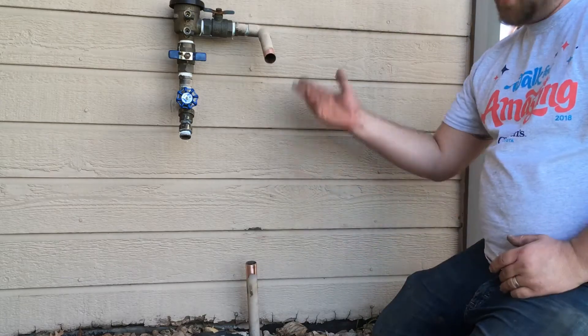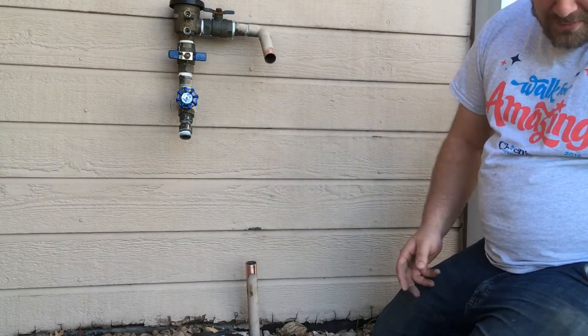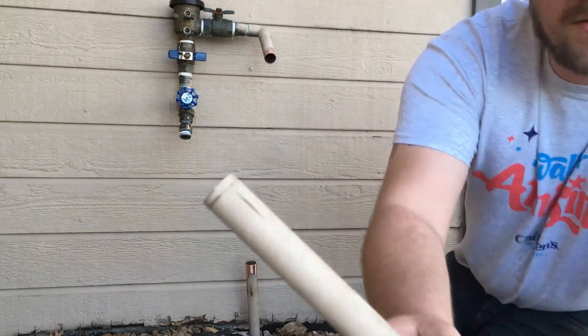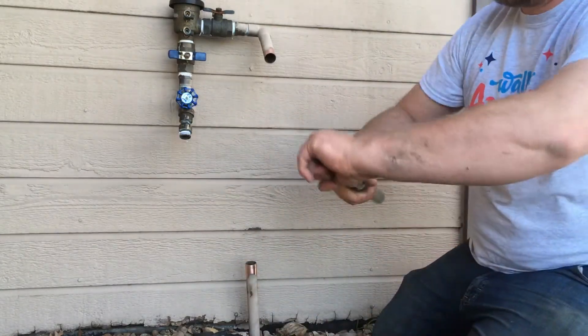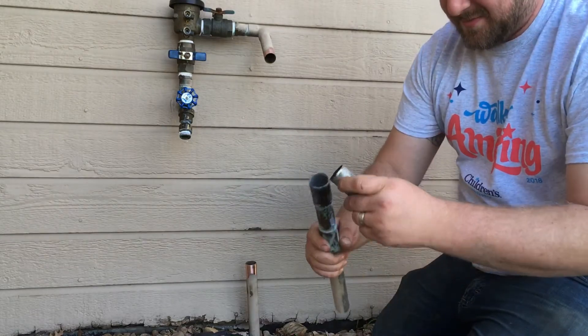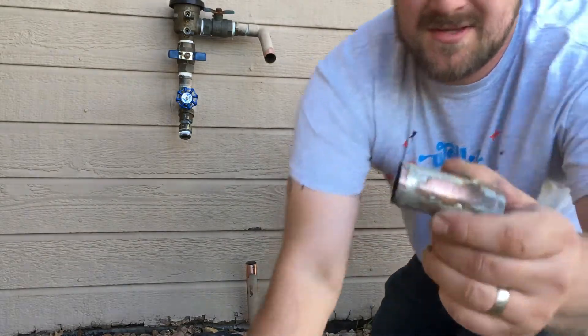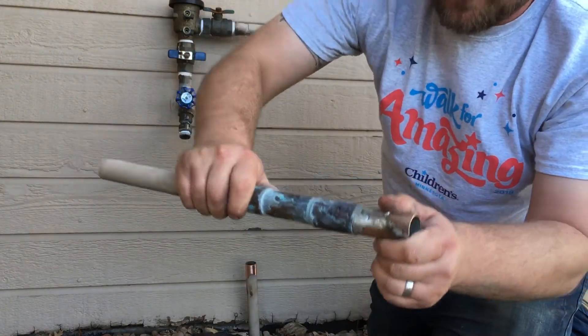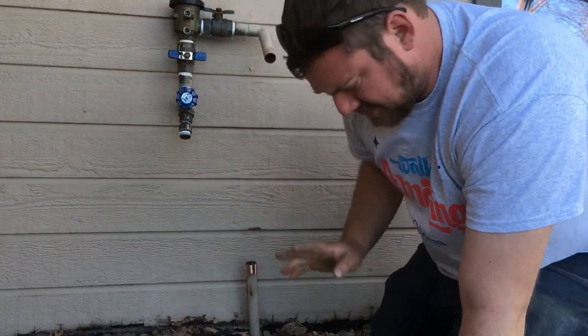I'm going to show you today how to replace or repair a copper down leg. This one has a crack in it right there, and it also has a bad solder joint that let free from the bottom. You can see where that line is — the pipe was only in that far before.